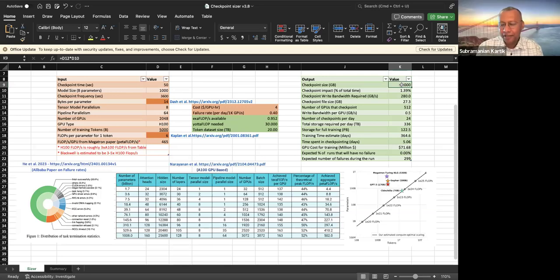Oh yeah, 100% agree, guys. These are enormously power hungry systems. Okay, so if I look at, say, H100 class HGX or DGX system, the average power draw for an 8 GPU system is 10.4 kilowatts. That's massive. Okay, and now if I want to say run 4 of these in a rack, I need a rack which is about 45 to 50 kilowatts in a rack. Most data centers for enterprise have 8 kilowatt racks, 10 kilowatt racks, 15 kilowatt racks on a good day. Almost nobody has 40 kilowatt racks.